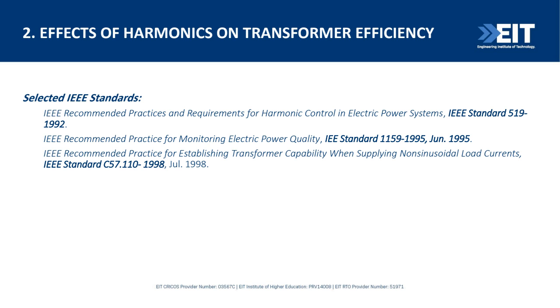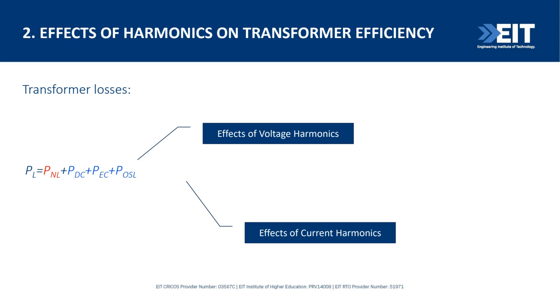We also have another IEEE standard, C57.110, published in 1998, with the latest version in 2018, which is the recommended practice for establishing transformer capability when supplying non-sinusoidal load currents. So if you want good insight into best practice for researching harmonics and how they affect transformers and cables, you can look at these standards.